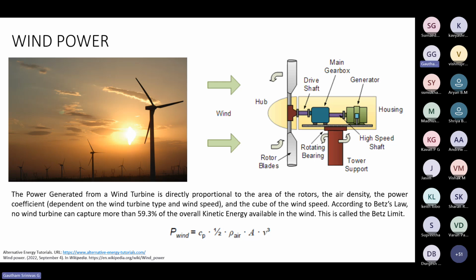So the power generated is directly proportional to the swept area of the rotors, the air density, the power coefficient, and the cube of the wind speed. This is basically the formula for calculating power generated from a wind farm. CP is the power coefficient - the maximum power coefficient can be 59.3%, called the Betz limit. You cannot extract more than 59.3% of the kinetic energy of the wind. That's the scientific principle here.